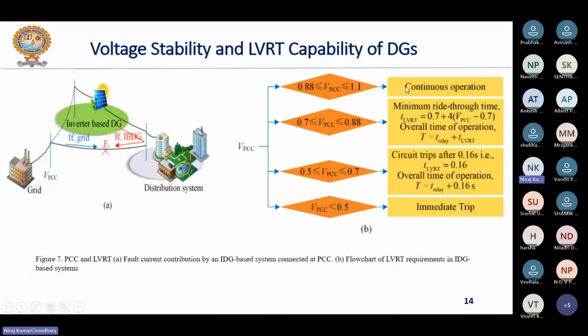Now when the voltage is in the range of 0.7 to 0.88 per unit, then this is the derived expression of the time of operation, that is TLVRT, means it is 0.7 plus the term mentioned here. So whenever you are calculating the time of operation of the relay, then you will have to add the calculated TLVRT with the time of operation of the primary relay, right? So that will be basically the total time of operation taken by the relay to sense that particular fault, right?